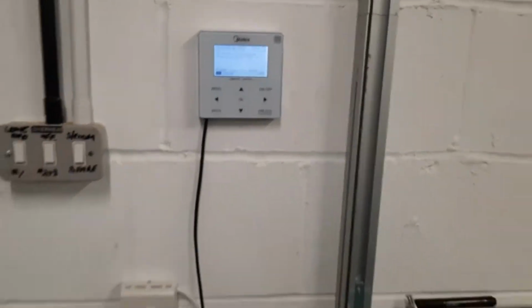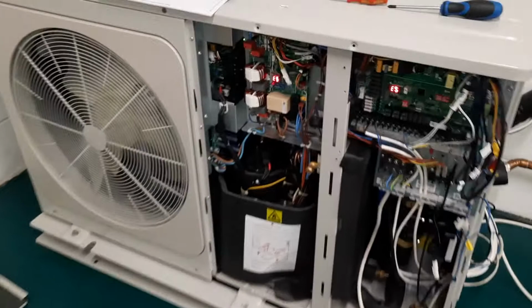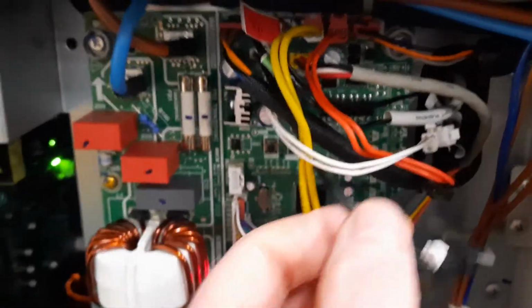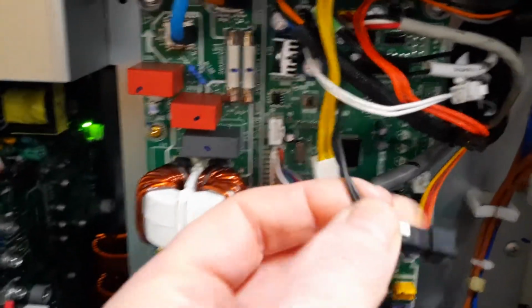So if we go to our unit and we take off the middle panel here where the compressor is, remembering to remove the screw here before we get the panel off, the sensor we're looking for is in the middle of the PCB here, and it's the black one. This one here, you can see, and if you look carefully, this is plugged in right up in the board at the top here into a 4-pin plug. In this case, this plug has been disconnected from here.